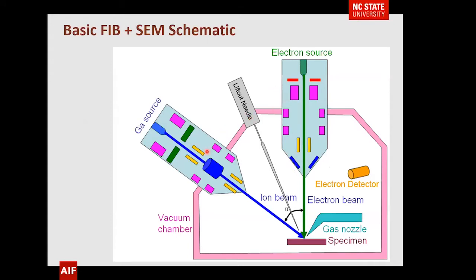Here's a schematic of our instrument — many instruments are very similar. You have an electron column here for the SEM. At a specific angle, in our case 52 degrees, you have a gallium source which is your ion source. The 52 degree angle enables you to be cutting the sample and then, without moving the sample, take a secondary electron image with the SEM. You also have a lift-out needle, gas nozzle, electron deflector, and detector.